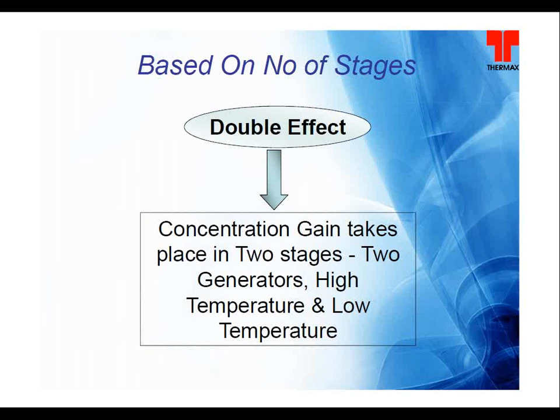So going by efficiencies, the COP, coefficient of performance, which is a terminology used in the refrigeration cycle, for single effect cycle is maximum 0.74, whereas the COP for double effect cycle is 1.42. Apart from that, even though it is not mentioned in this presentation, there is a triple effect cycle which Thermax has pioneered, and we are the only company in the entire globe who has presented and successfully installed this triple effect machine in a nearby area of Delhi itself. The COP of this triple effect cycle is 1.7.